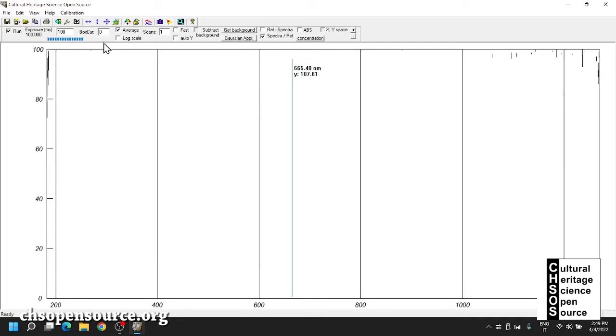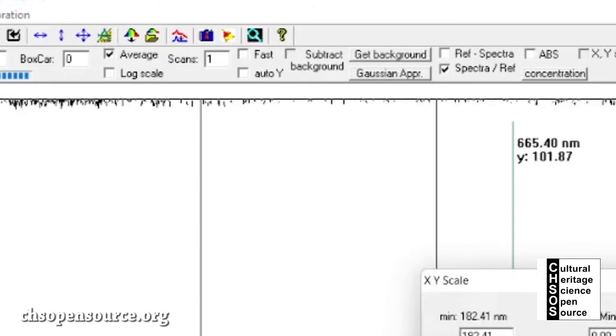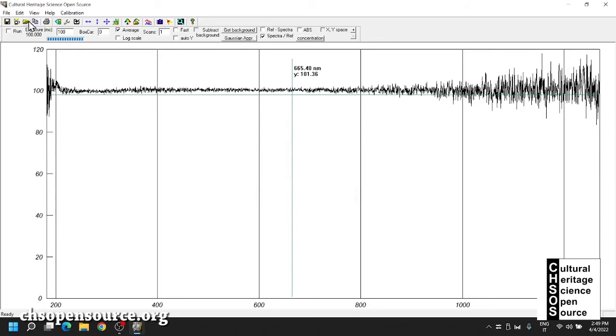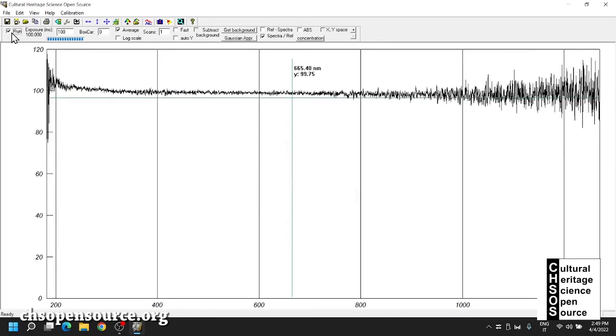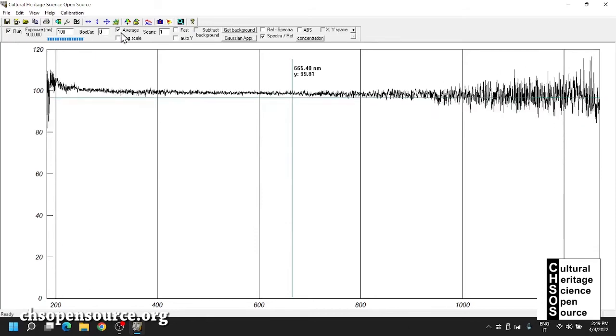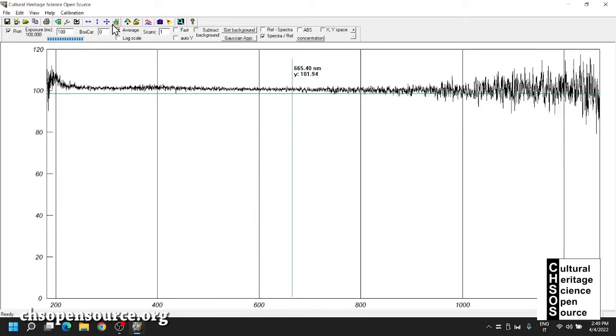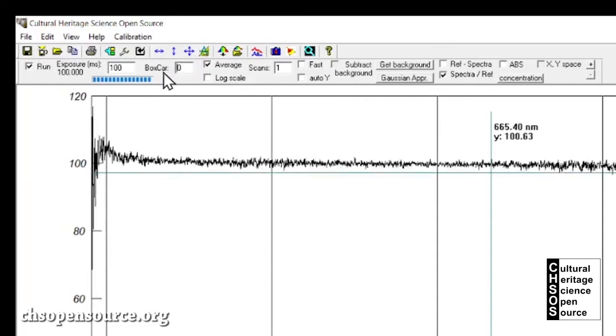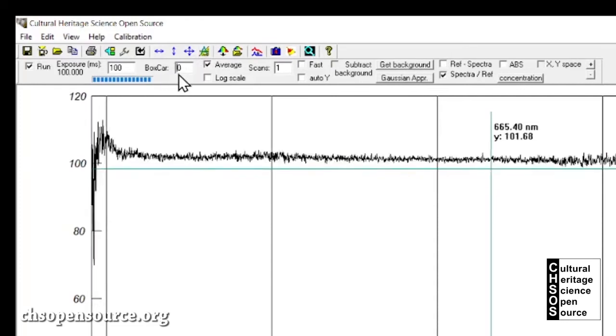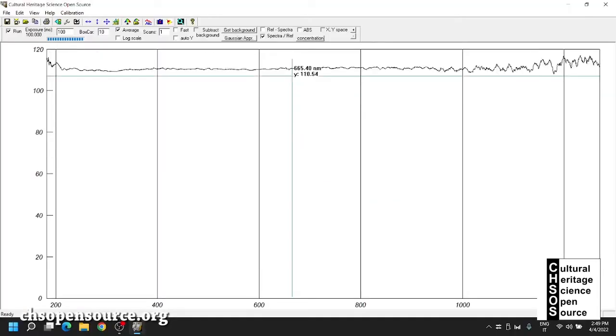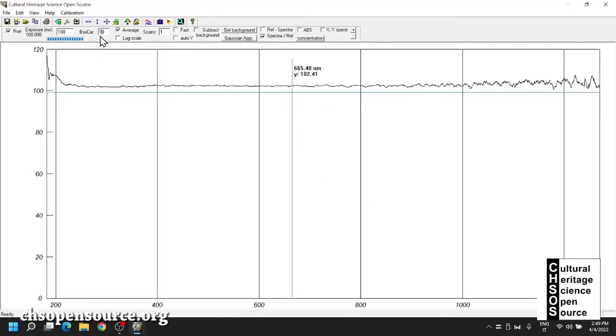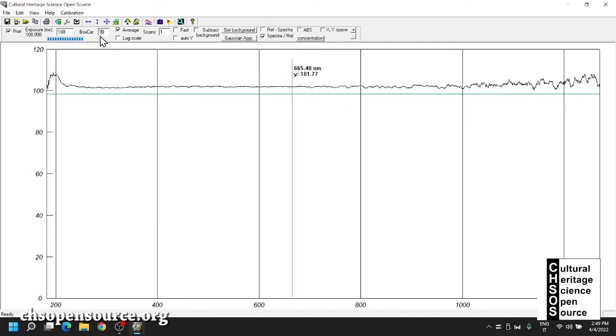So you see now we are seeing the spectrum as a reference, as a reflectance spectrum between 0 and 100. It's a good idea to change the scale, and here instead of 0 and 100, let's put 120% in order to see a little bit of the fluctuation. Okay, there it is. Also, it's a good idea to introduce a little bit more boxcar. So it is this value over here, boxcar, and instead of 0, put 10. This is useful because we reduce the noise in the spectrum, so we have smoother spectra.